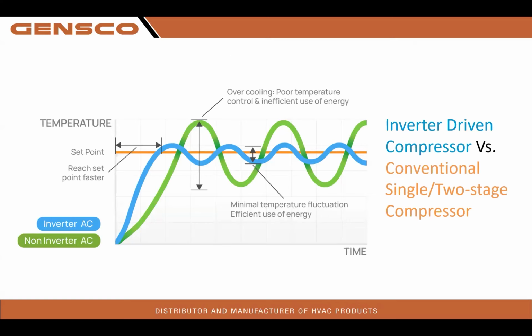Less stop and starts. We want longer run times at a lower modulation, which is going to give us better energy efficiency at the end of the day. Less amp draw, longer run times, low modulation, period. Actually, this equipment is kind of designed to run 12 to 14 hours a day at a very low modulation. Think mini split, but in a unitary application.